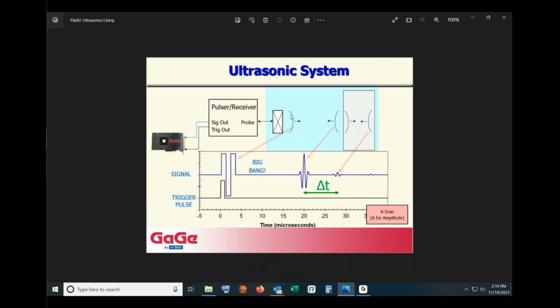After emission of the ultrasonic pulse, it travels towards the sample, and you get a reflection from the front wall of the sample that we see here in the ultrasonic signal, this big echo here. But not all the ultrasound bounces off the front wall. Some of it enters into the sample, travels to the back wall, and then bounces off. So it makes a round trip through the sample, and we get this back wall echo here. In fact, the sound bounces back and forth, so you get echoes reverberating with an equal delta T until they die out.